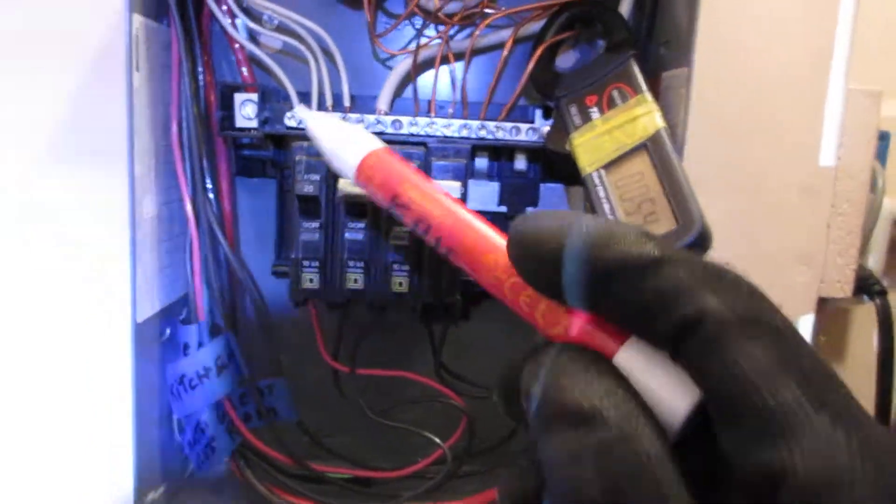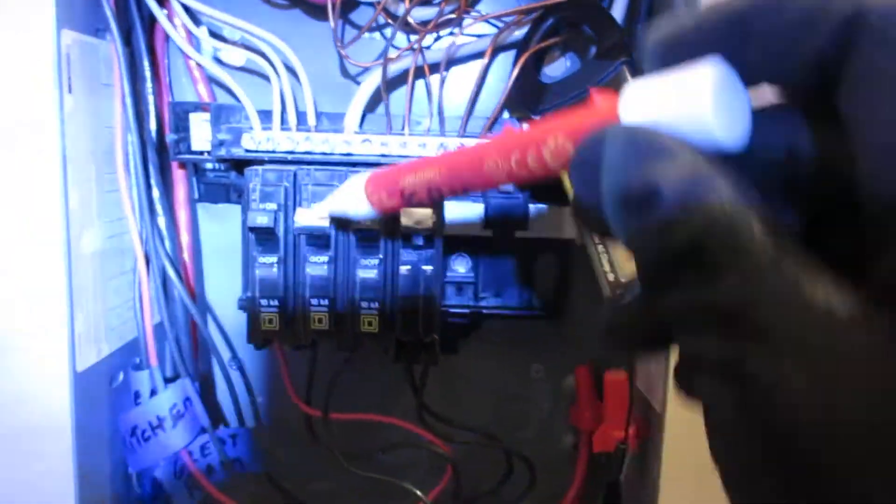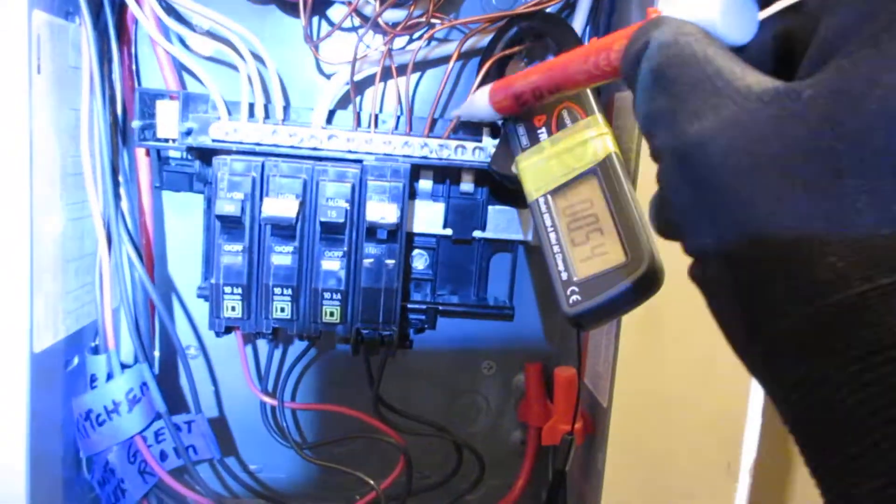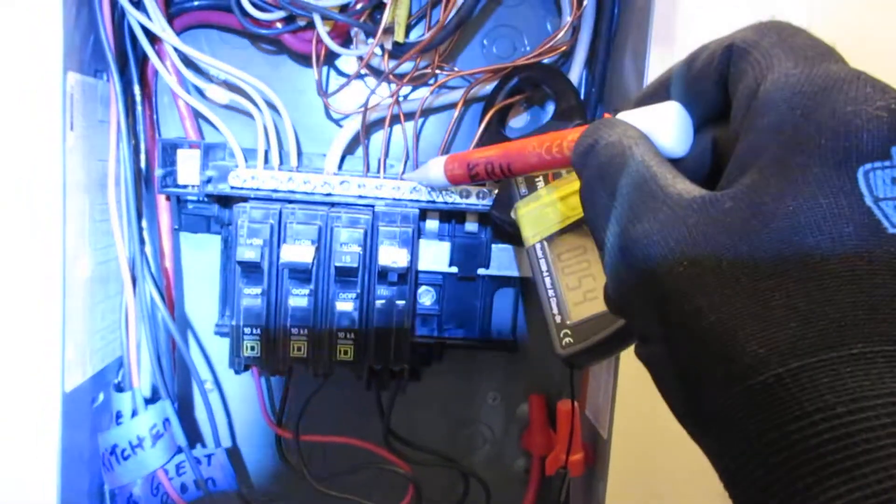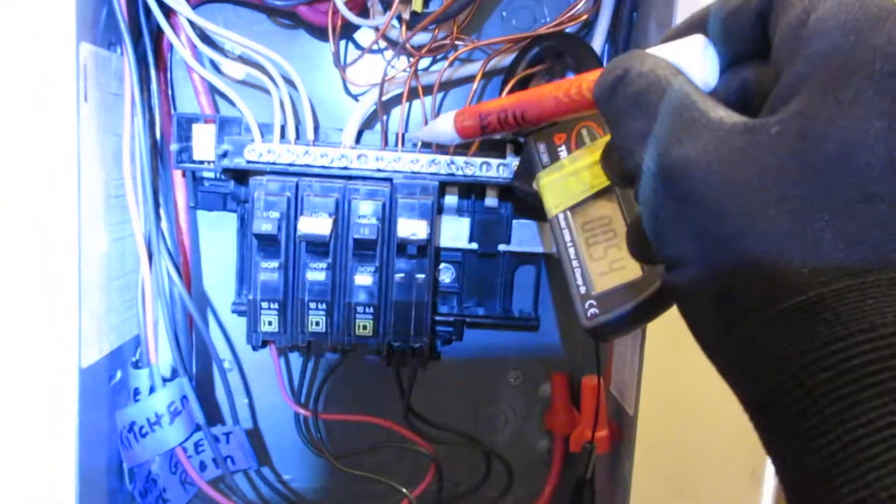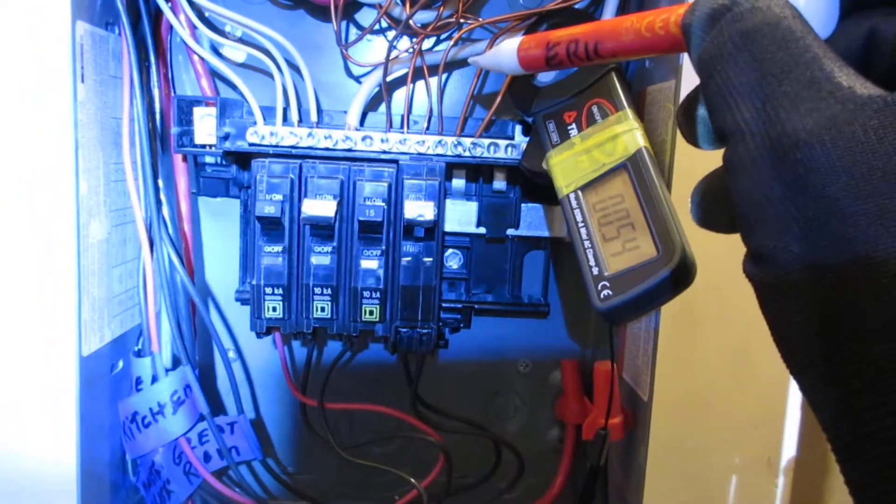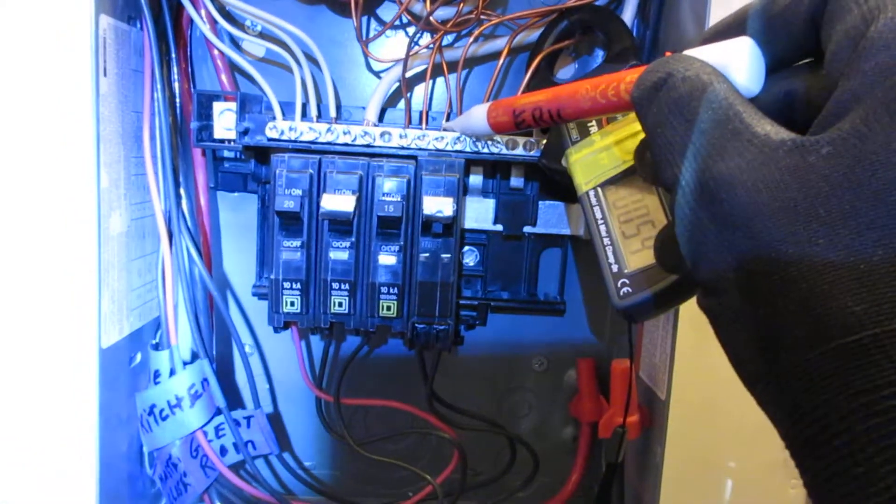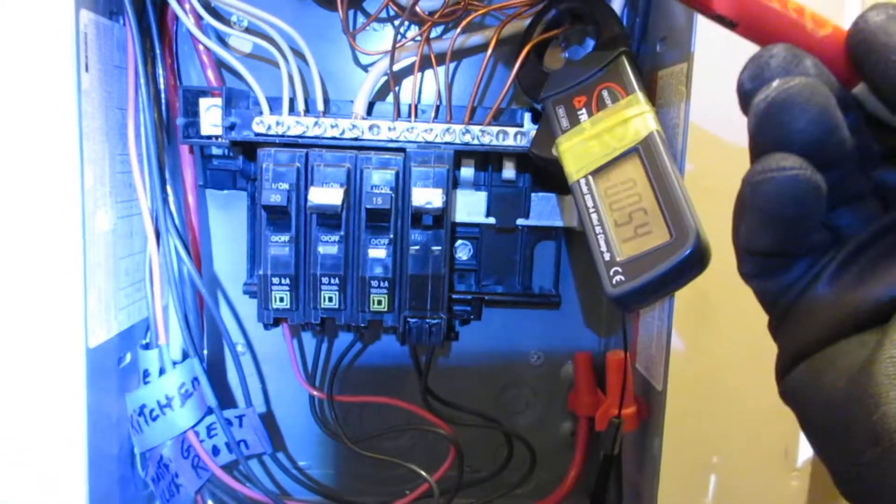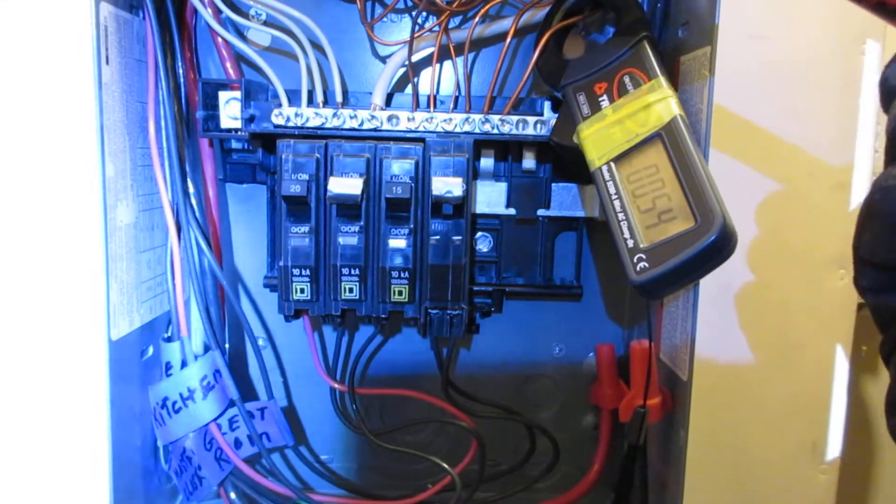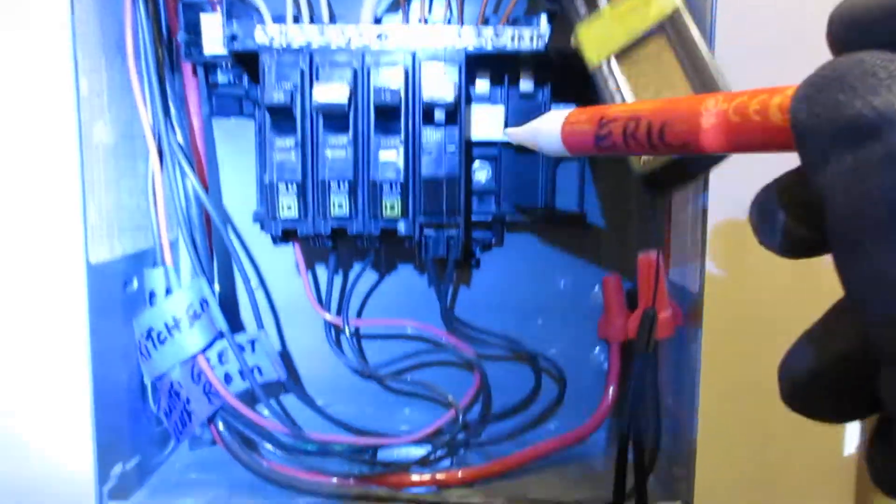Now look at this. This is a sub-panel, but they have all the neutrals and grounds connected on the same bus bar. Okay, this is a categorical mistake. They can only be connected on the same bus bar back at the service entrance and that's 100 feet away. So there's no second bus bar for grounds or neutrals.